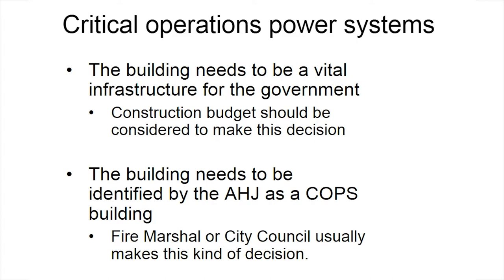These facilities are ones that the government decides, one way or another, are critical for the operation of this country. It's important that, at the time the project is being created, even when the city or the state or whoever is going to issue the bond, the facility is aware early in the stages that it's going to be a COPS facility or have a COPS portion. What we have learned is that if you don't make the decision early in the process, even before you go for funding, you might find out it increases the cost significantly just to try to comply and make this facility mission critical, making sure the facility doesn't have any single point of failure.